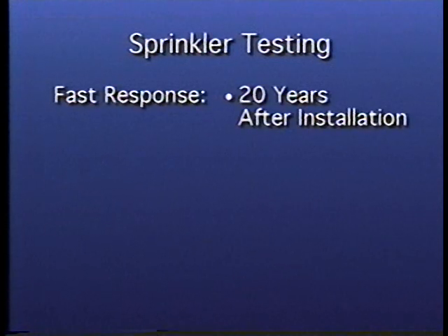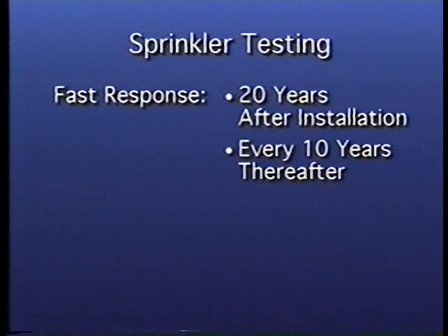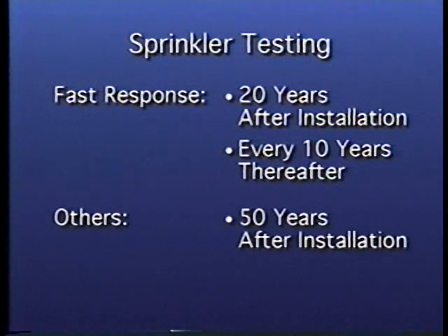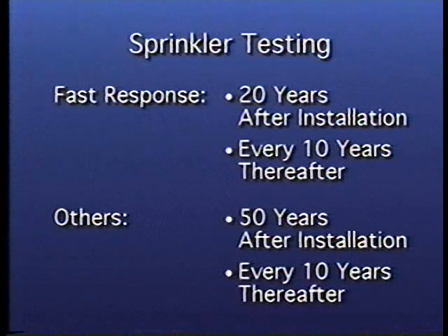A functional test of the automatic sprinklers is to be performed 20 years after installation and then every 10 years thereafter for fast response sprinklers, and at 50 years and every 10 years thereafter for other sprinklers. These tests should be performed by Underwriters Laboratories Incorporated or Factory Mutual.